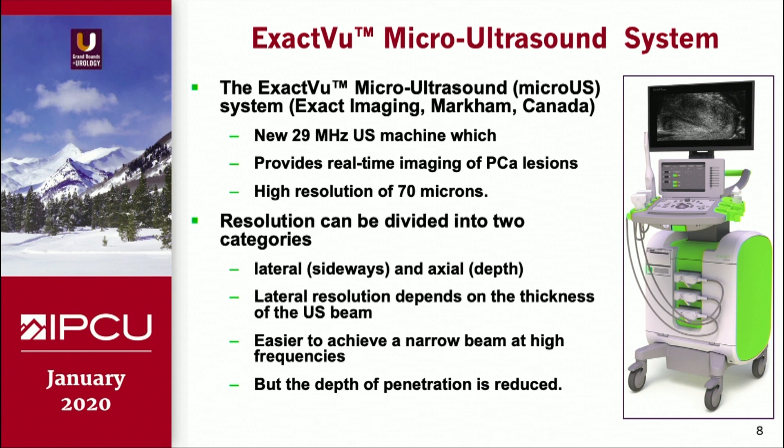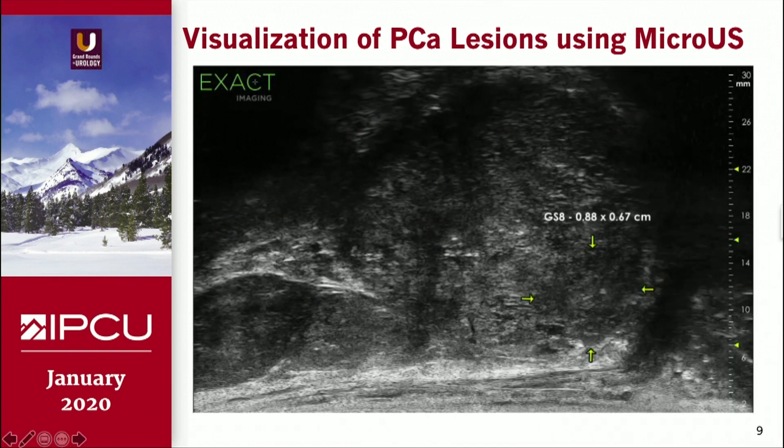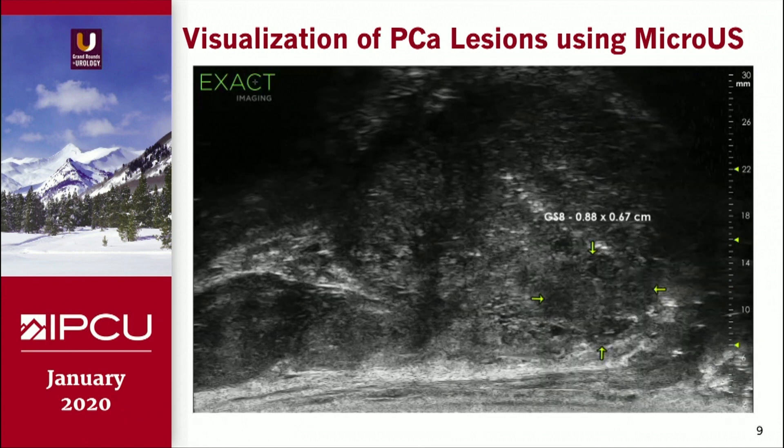ExactVu has introduced this new ultrasound machine. It operates at 29 megahertz and provides real-time diagnosis of prostate cancer lesions, with very high resolution of 70 microns. The resolution can be divided into two categories — lateral and axial. Lateral resolution depends on the thickness of the ultrasound beam, and is easy to achieve for narrow beams at very high frequencies. But when you achieve that, the depth of penetration becomes far less. This is a video from their website where they are targeting a cancer lesion for biopsy purposes.